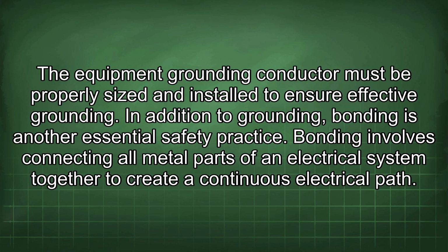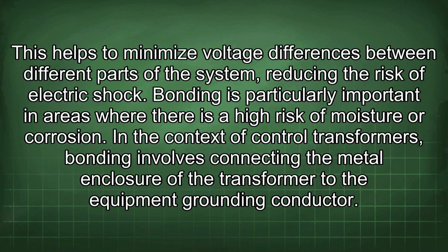In addition to grounding, bonding is another essential safety practice. Bonding involves connecting all metal parts of an electrical system together to create a continuous electrical path. This helps to minimize voltage differences between different parts of the system, reducing the risk of electric shock. Bonding is particularly important in areas where there is a high risk of moisture or corrosion. In the context of control transformers, bonding involves connecting the metal enclosure of the transformer to the equipment grounding conductor.